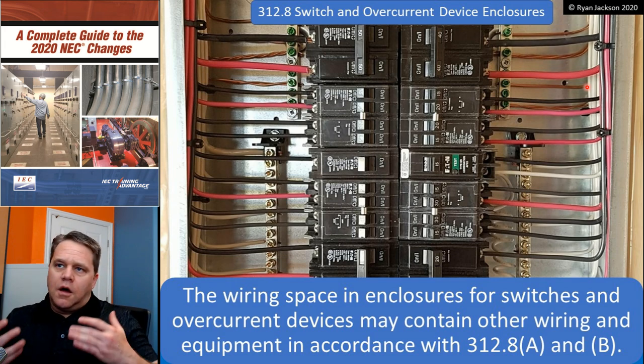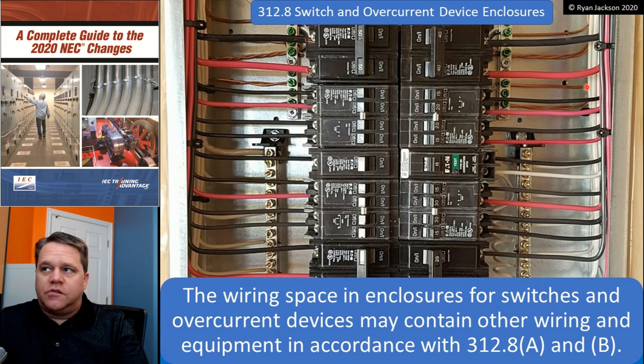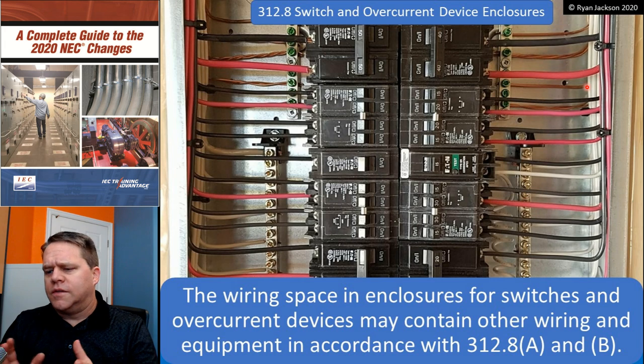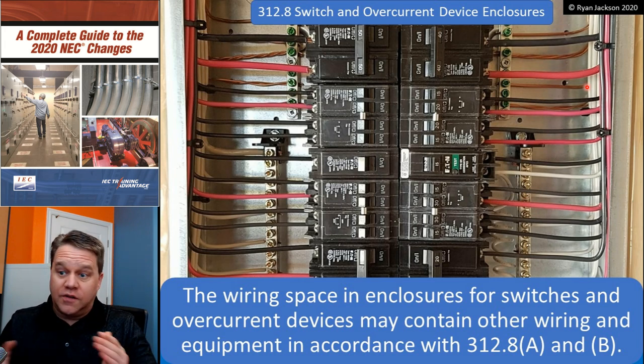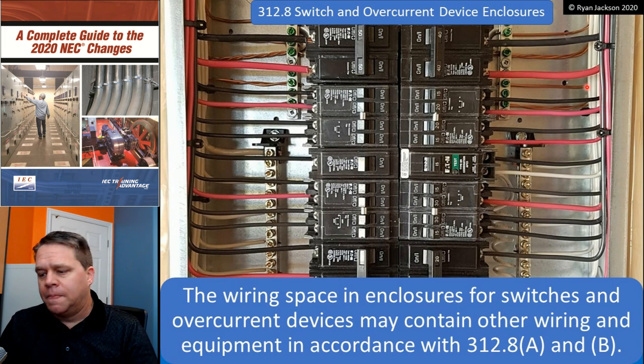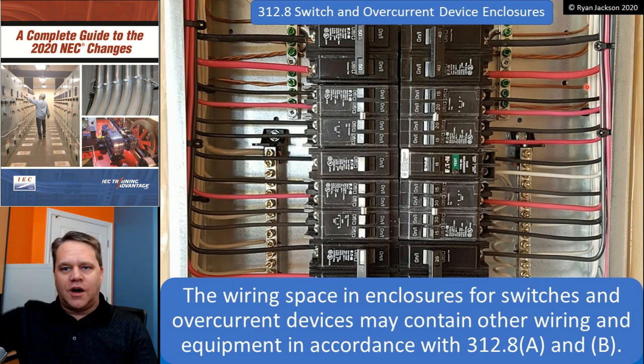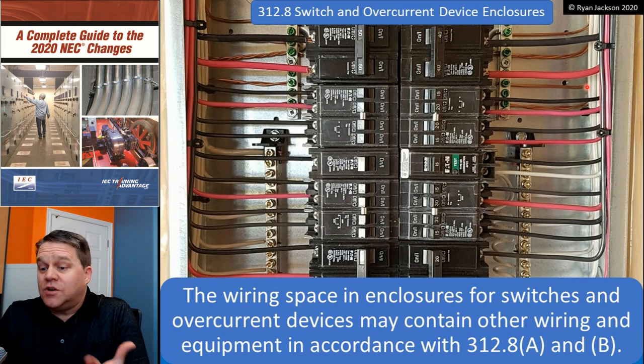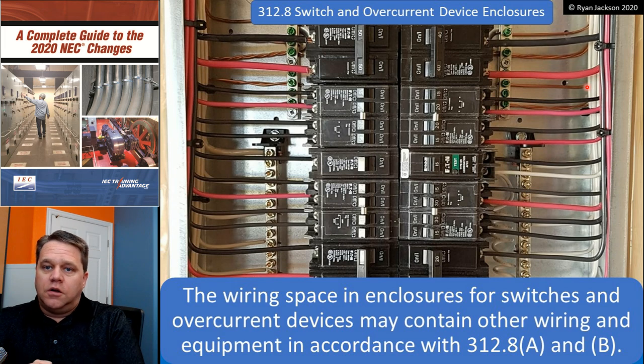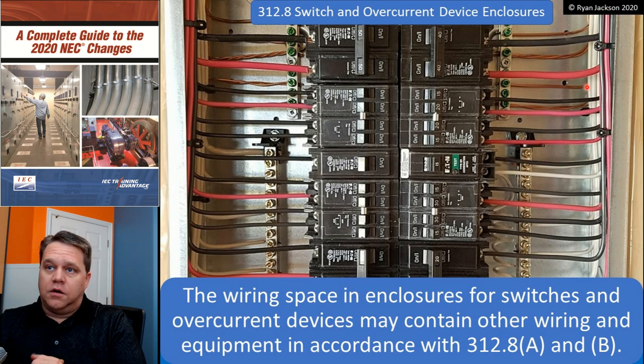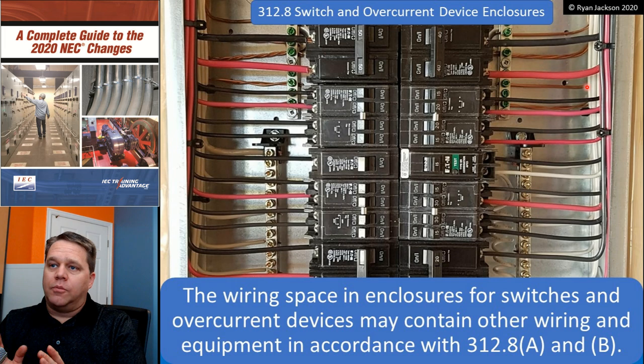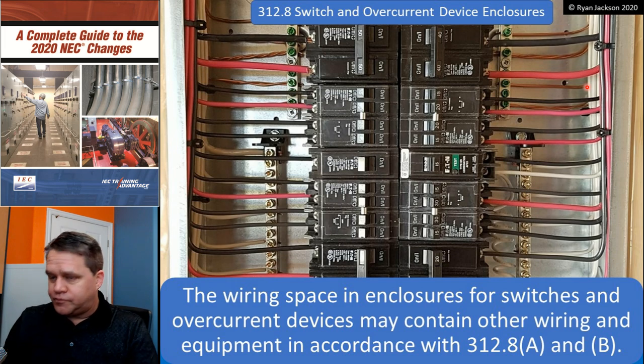We're in Article 312, which covers cabinets, cutout boxes, and meter socket enclosures. A lot of people get confused on what those are. A meter socket enclosure is self-explanatory — it's the enclosure a utility meter goes in. A cutout box is a switch enclosure — when you have a fused switch, you install it in a cutout box. A cabinet is what we're looking at in the photograph: that's a panelboard mounted in a cabinet. The cabinet is the enclosure; the panelboard is actually just the guts — the bus bars.